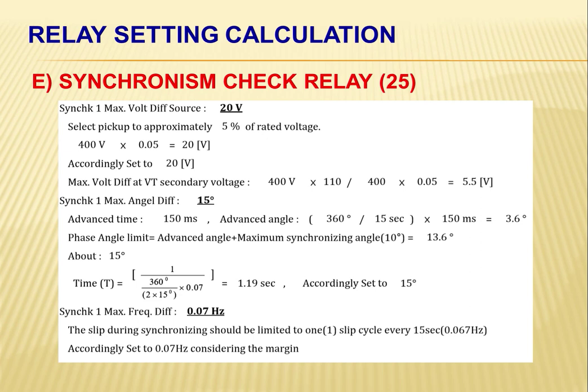For the voltage, 2 power sources that are to be paralleled ideally need to have the same voltage. If 2 power sources with unequal voltages are paralleled, it causes reactive power, VAR, to flow between the sources. Minor variations of 1 to 5% can usually be tolerated. That's why we set 5% of rated voltage. VAR flow will cause unnecessary heating in interconnecting components if it is beyond that 5%.